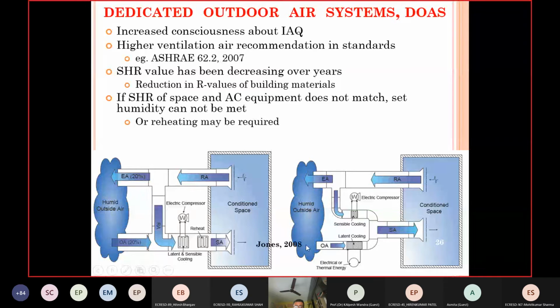Okay. And as compared to that, if you adopt a dedicated outdoor air system, what will be the scheme? The scheme will be like this. This is the return air, and you are exhausting it here, and this is the recirculated part, and this recirculated part you are cooling with the conventional system, but for the outdoor air that you are taking here, mainly latent cooling is done here, right? There could be some sensible cooling also, but mainly it is taking care of the latent cooling, that is removal of moisture, and you will remove moisture to a level where it can also take care of the latent load in the space, not just the latent load of the outdoor air, but also that of the conditioned space, and then you mix it and supply it.